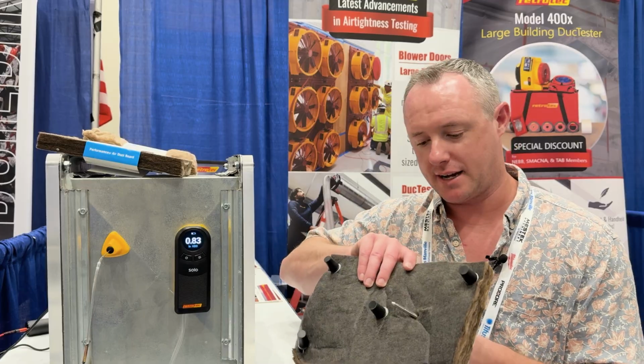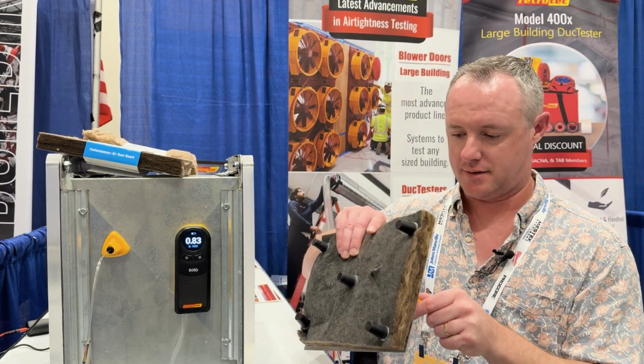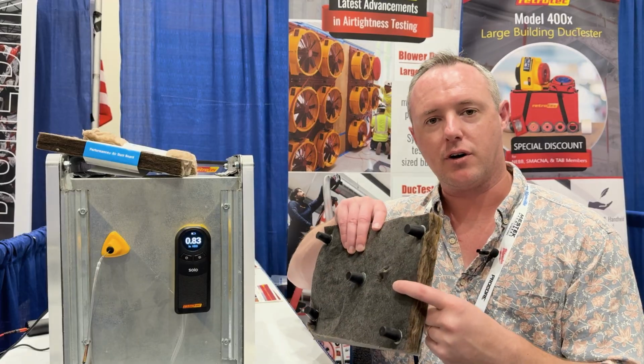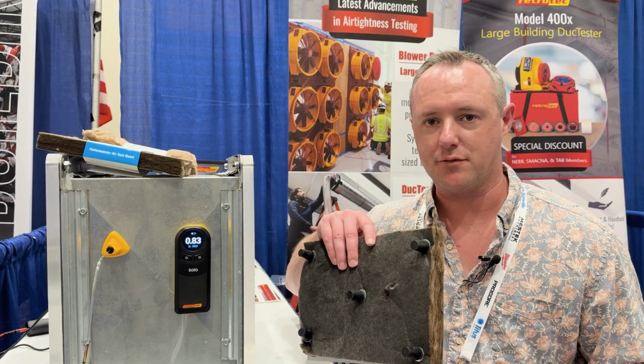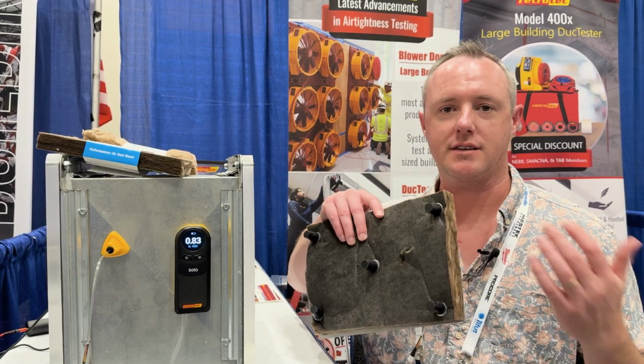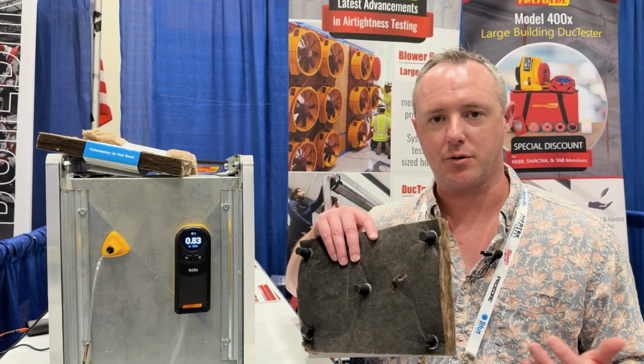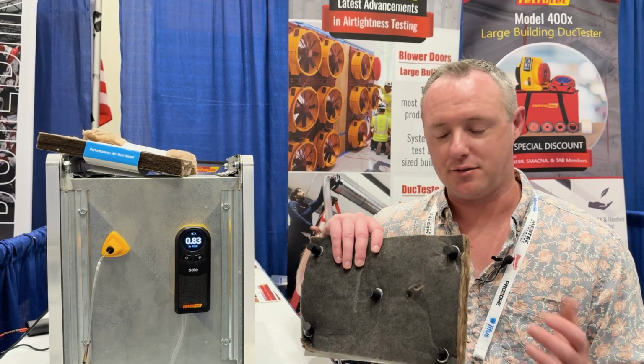So instead of reading static pressure, you can be reading velocity pressure by accident. If we take this probe back out and put in the multi-probe, now we're always going to be perpendicular to the airflow. We're never going to have an opening directly into the airstream where we'd read velocity pressure, because we don't want to do that.